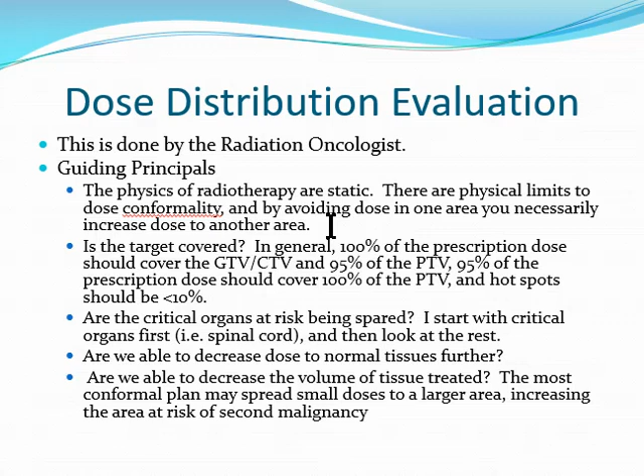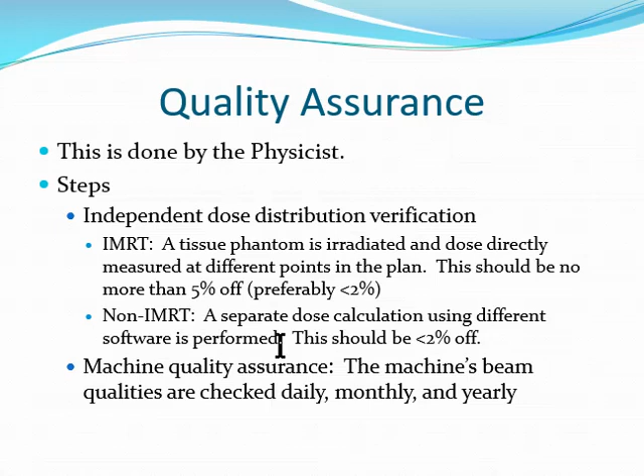Once I've approved a plan, it needs to be double checked by a physicist, and they look at each individual plan. They'll actually irradiate a kind of fake patient, a phantom, to see if the actual dose being delivered in the phantom is within a certain tolerance of what we predicted. For non-IMRT plans, we usually use a different set of software to do an independent dose calculation. The physicists are also involved in the machine quality assurance, because over time, we want to know that the beam is reliable, that the software is reliable, and that what we believe we're delivering, we are in fact delivering.